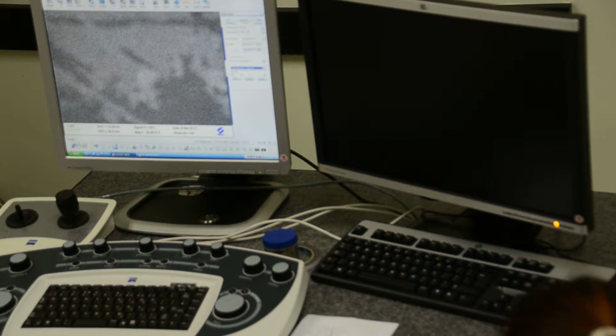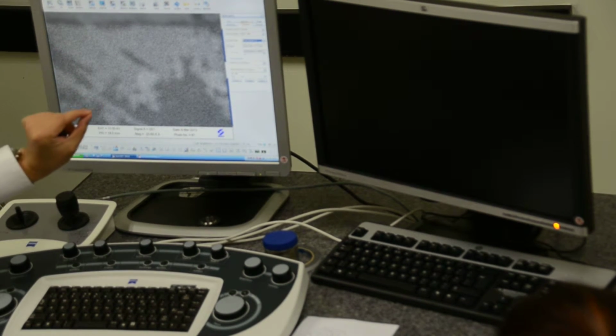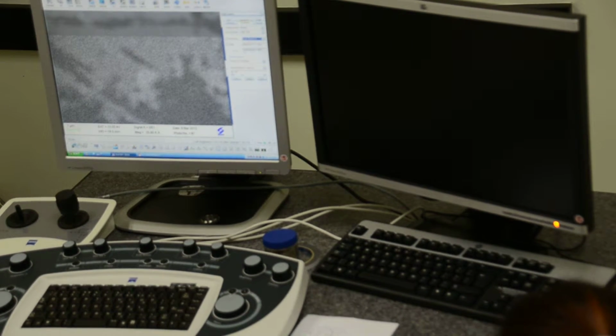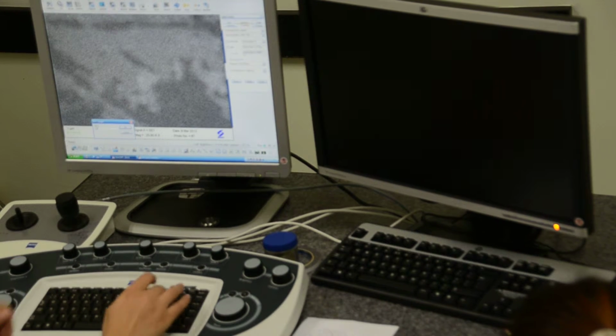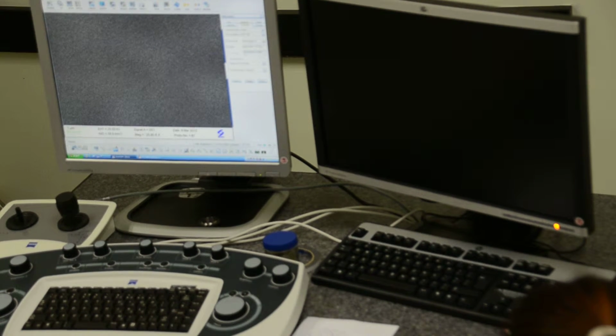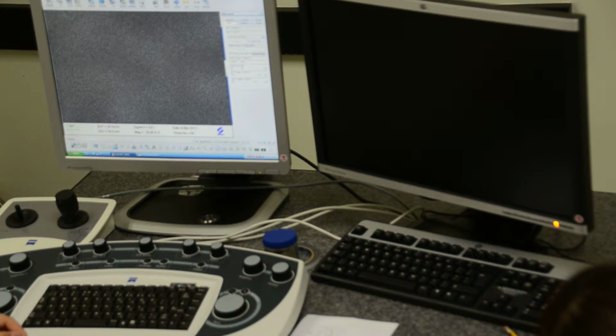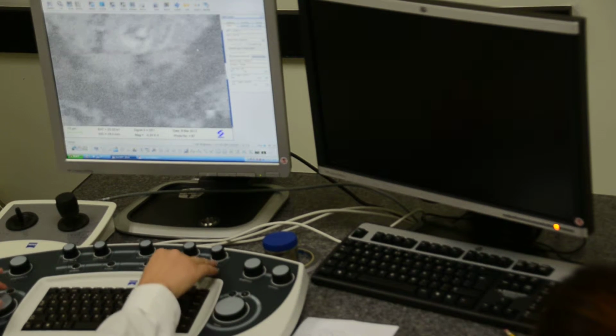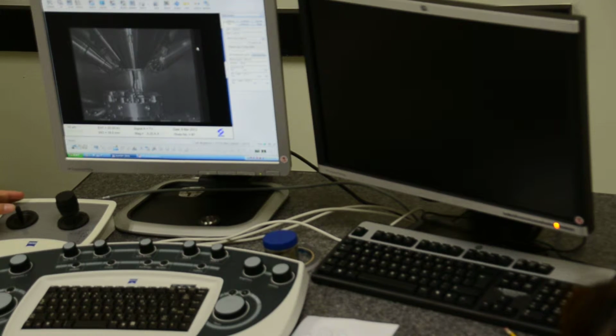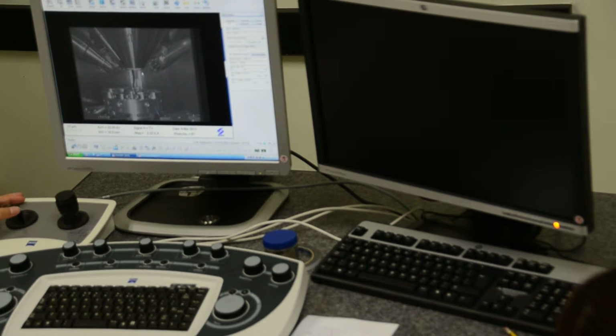Then during the scanning, just now I told you to go to 9 average, n equal to 60, scan speed 3. But now over here that is not good enough. You have to go to scan speed 5 to have a reasonable resolution. So okay, why don't we have a try to get a slightly better image quality. I go to 20 kV, I'm not going to 30. For probe current, I go to 50. You want to get a good image quality, you want your sample to be close to your column.